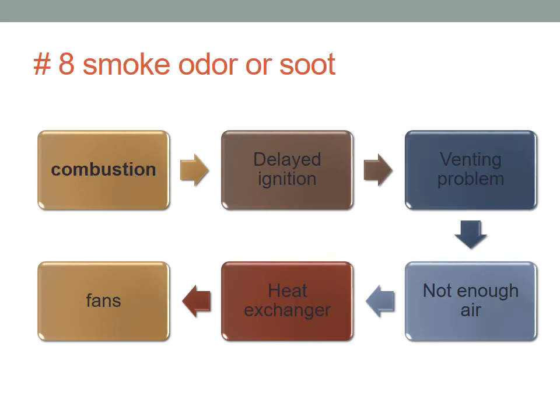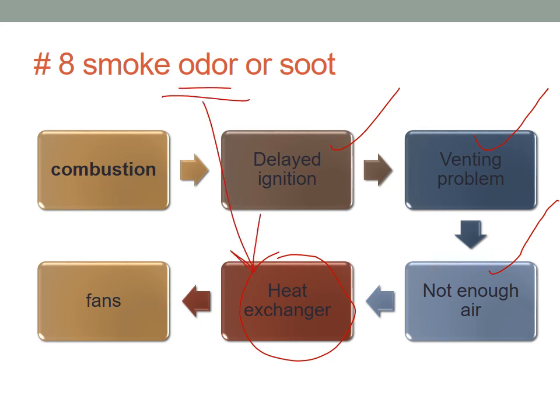Okay. If you have smoke, odor, or soot, it's always a combustion problem. It could be caused by delayed ignition, a venting problem. We don't have proper venting, or there's a crack in the vent. Could be not enough air, so we have incomplete combustion. And if the heat exchanger is broken or cracked inside the furnace, probably you'll have an issue with smoke, odor, or soot, mostly odor, because you'll smell the combustion fumes. Also check the fans, they could be leaking at some point or giving off too much pressure. That's not the design pressure for the duct.